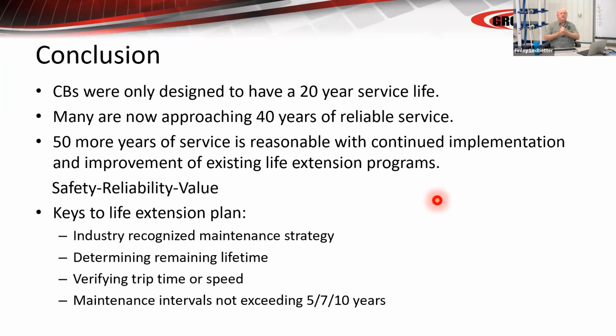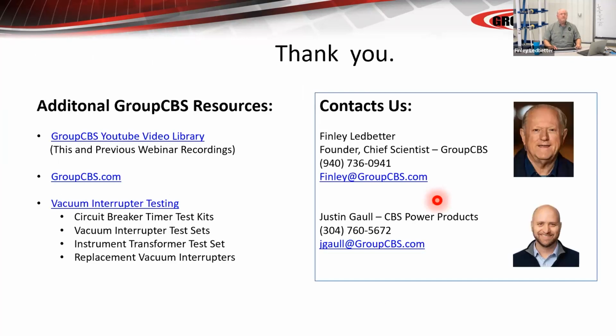Are you ever going to be able to replace it? Verify the trip times occasionally to make sure mechanically it's okay. And maintenance intervals not exceeding 5 years, certainly not 7 or 10 generally for inspections and cleaning. Okay, so be careful there. That's my recommendations. I've only been doing this 45 years. I guess I could be wrong, but that's what I recommend.